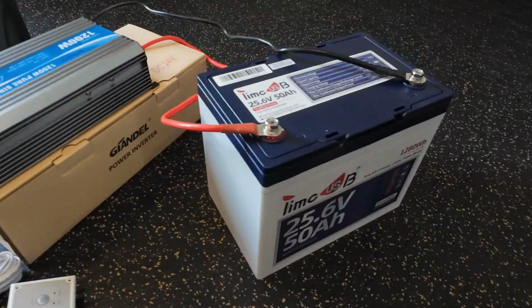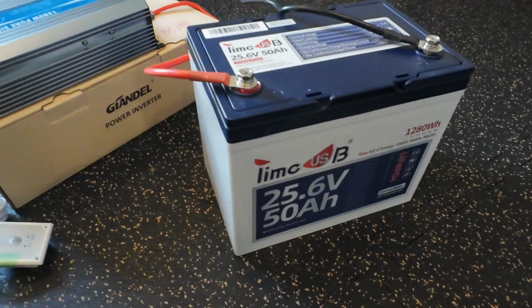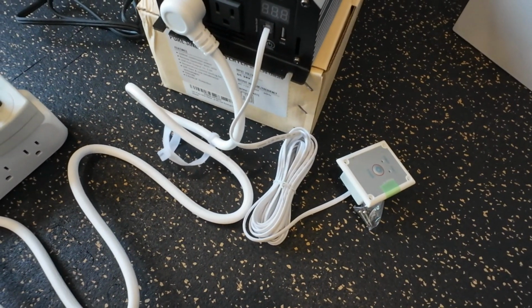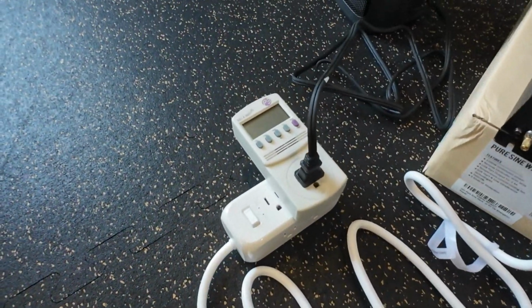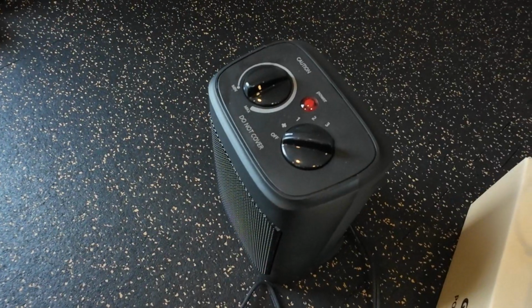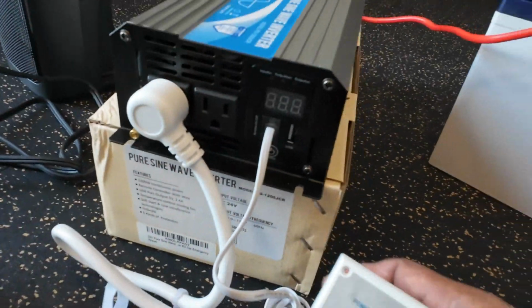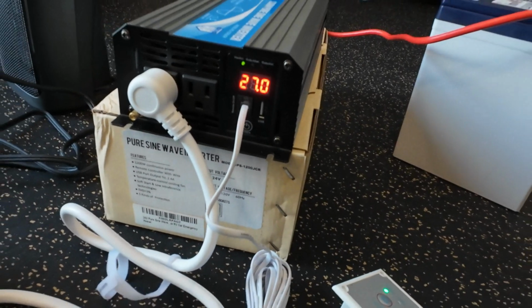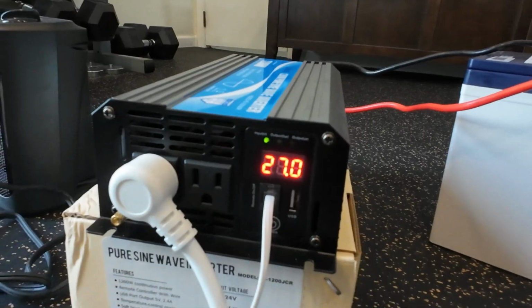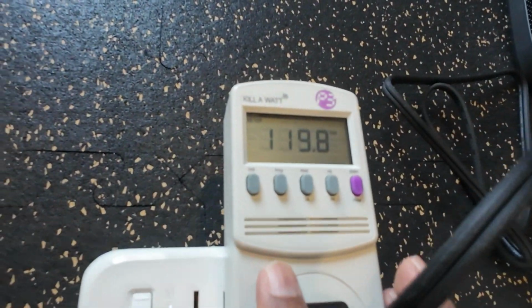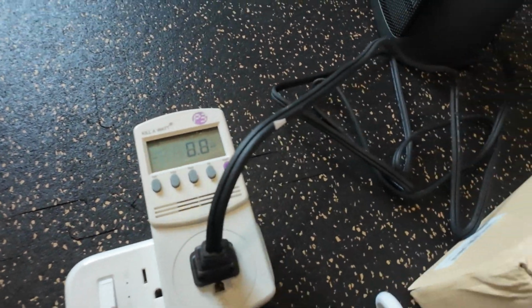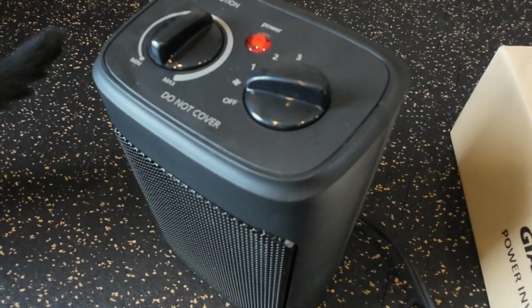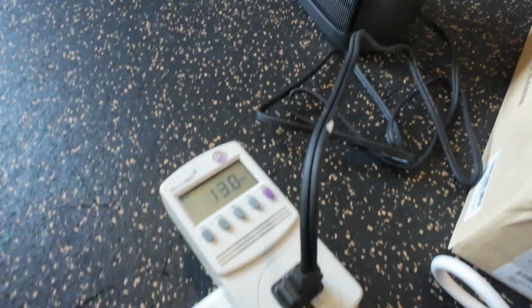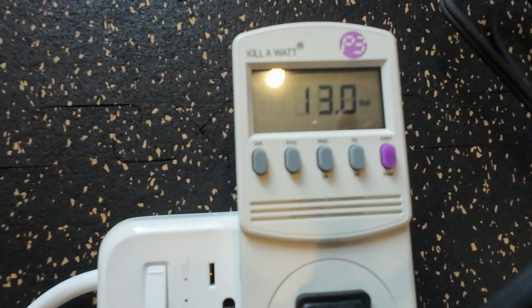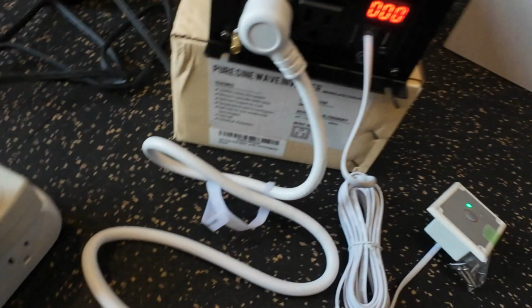Here is the test setup. Battery is connected to the inverter. Remote switch of the inverter is connected. I'm using a power strip here to connect a small space heater through a Kill A Watt meter so that we could monitor the wattage and amperage outputs. Here's the initial voltage reading. It's showing about 120. So I'm going to turn the fan on of the space heater without heat, and it is showing about 13 watts here. The inverter display does not show this small power output.